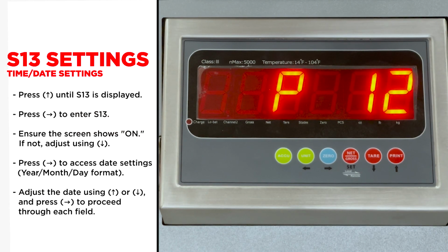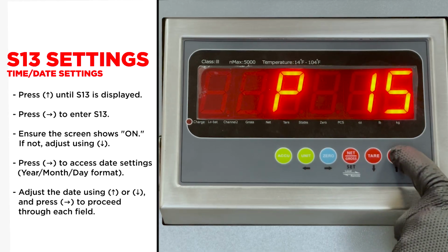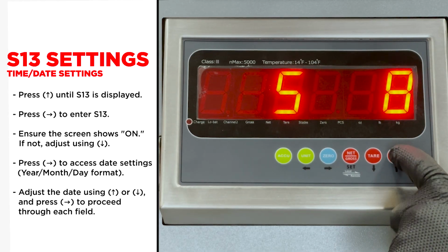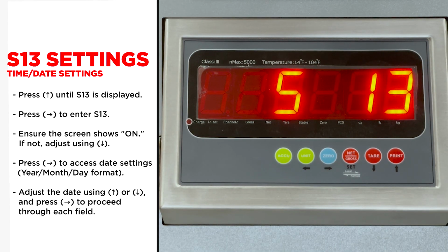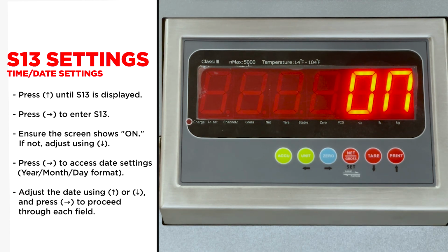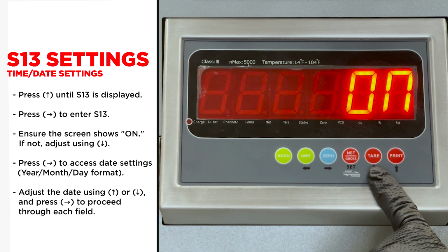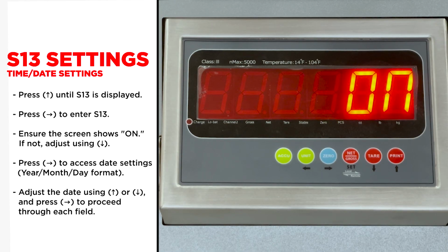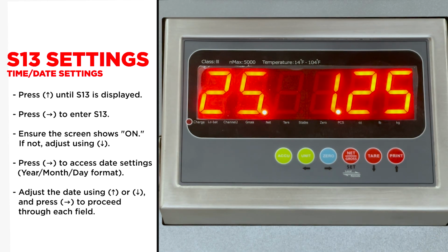Now press the up arrow until it shows S13. Now press the right arrow to enter and adjust S13 settings. The screen now shows on. If it does not show on, press the down arrow until on is shown on the screen. Now press the right arrow to enter the date settings. From left to right, it corresponds to year, month, and day.